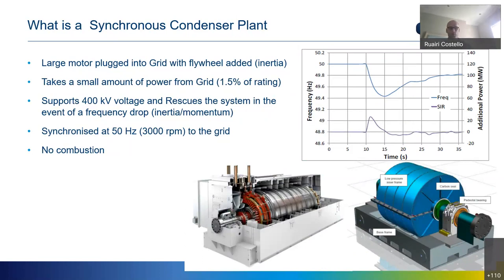And you can see the typical frequency curve in Ireland, for a much smaller system than the UK. It's quite severe, with rate of change of frequency of greater than 1 hertz per second. Synchronized at 50 hertz and 3000 RPM, and it's clean. There's no fuel, there's no combustion.